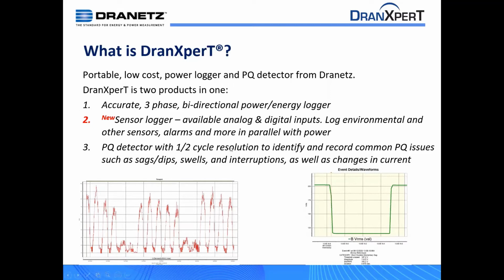Now, the new capabilities which we introduced just at the beginning of 2022 this year are the sensor logger capabilities. So there's actually 2 models available. One is available with analog and digital inputs. And when I refer to that, I don't mean our voltage or our current primary inputs. These are sensor and transducer inputs. So it'll connect to either a standard 0 to 10 volt or 4 to 20 milliamp standard transducer output for a variety of sensors that could do temperature, humidity, other environmental things, pressure, and anything you can dream of that produces those very industry standard outputs.